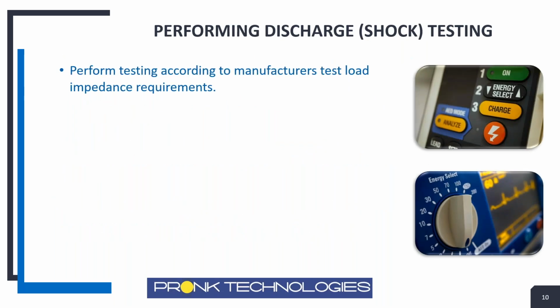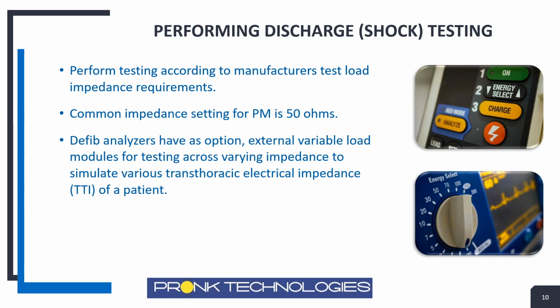So of course, the manufacturer requires these tests to be performed, and they require it to be done at a specific impedance. For the PM, you don't usually have to test it at a wide range of impedances, but the service manual will specify testing at X impedance. So you want to make sure your defib analyzer is set to that impedance, because if it's set differently, you're going to shift your results. You want to make sure that you've set it to the right impedance. The most common impedance, not 100%, but the most common, is to set the defib analyzer to 50. So that's what you want to confirm in the service manual.